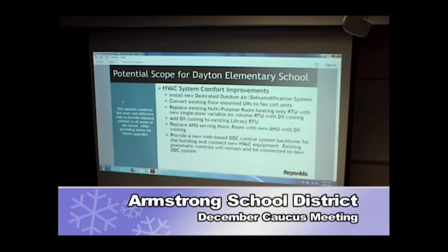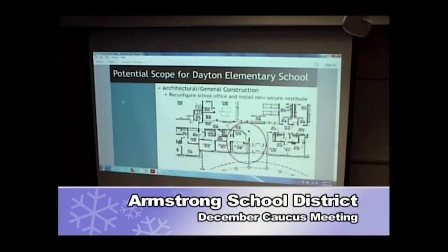So what we're recommending is putting in the dedicated outside air system, replacing the existing multi-purpose room air handler and adding actual DX cooling - full air conditioning - there, adding DX cooling to the library rooftop unit, replacing the air handler that serves the music room and putting DX cooling in there, and installing a new DDC or modern control system. All the new equipment would be fully controlled by the DDC system, while existing equipment currently on pneumatics would be controlled by the DDC but with limited controls. You don't want to put brand new sophisticated controls on old equipment - it's not a wise investment.